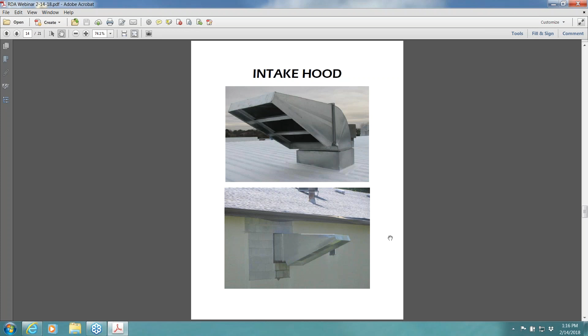Then you've got ductwork to consider. You've got to get the fresh air into the air makeup system. This is a hood style here. This is through the roof in this top picture, or through the wall in this bottom picture. Sometimes you try to avoid roof penetrations at all costs, and the intake is a good place where you can take that out the wall. The biggest thing on intake versus exhaust is they have to be 10 feet away. That's a code requirement.